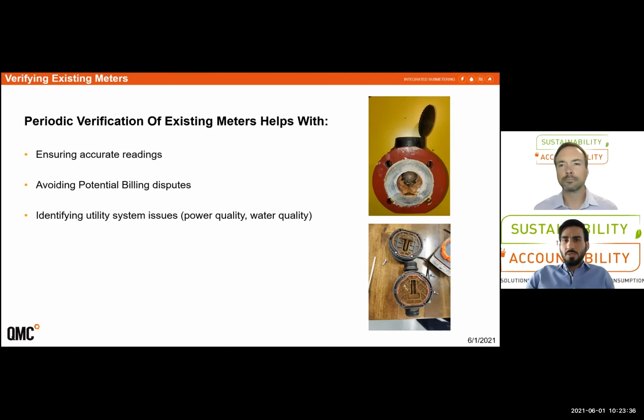I also wanted to go over the importance of periodic maintenance of the metering equipment, regardless of them being used for cost recovery or billing or energy management purposes. I really want to single out the mechanical meters, such as the positive displacement type meters or the impeller type meters commonly used on the domestic water applications, or the insertion turbine type meters used for flow measurement in thermal energy calculations.